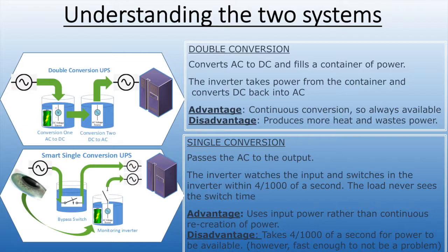It's always coming off the battery and off of the DC bank, so there's never a downtime. On the lower single conversion, you see the power comes in and it goes right back out to the load. The eyeball represents the electronics watching the grid, and if the grid fails, it immediately opens the grid, removing the grid, and it closes the battery.